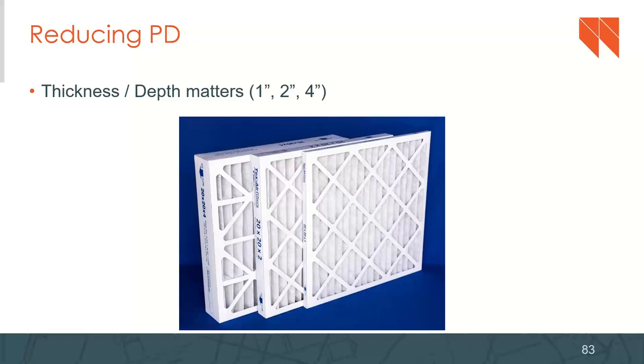You can get MERV 13 in the standard 1 inch filter, but a thicker filter with that MERV 13 rating is going to have a lower pressure drop. There's just more surface area for the air to move across, and you're going to reduce that pressure drop.